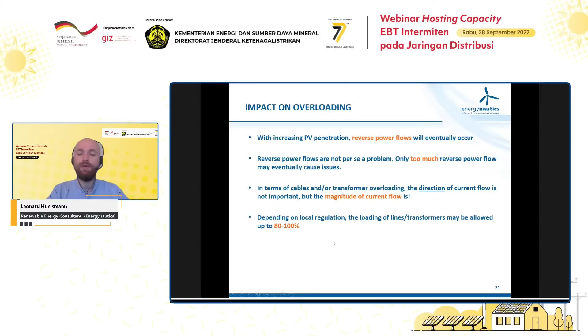Here's a short example from the Dominican Republic again, where on the left side we are looking at the maximum demand if there's no PV generation, and we observe for this distribution network a maximum line loading of 55%. And actually, when adding a very high amount of PV generation in comparison to peak demand, we still don't observe overloading here. And so these kinds of assessments can help you figure this out.